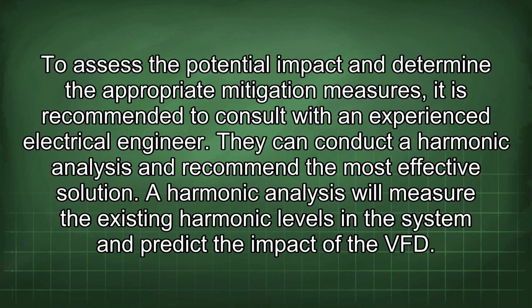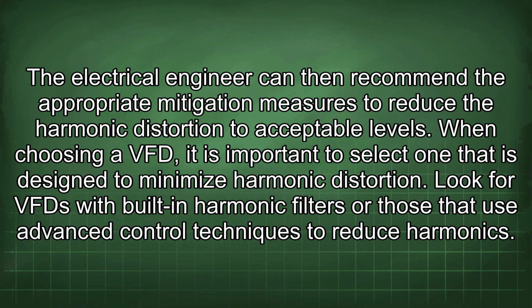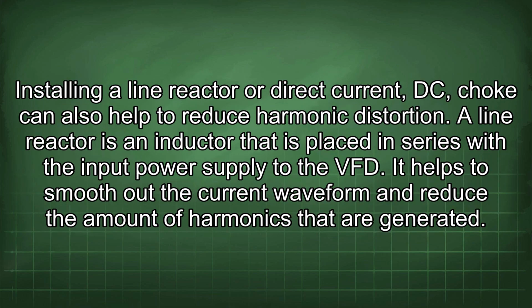To assess the potential impact and determine the appropriate mitigation measures, it is recommended to consult with an experienced electrical engineer. They can conduct a harmonic analysis and recommend the most effective solution. A harmonic analysis will measure the existing harmonic levels in the system and predict the impact of the VFD. The electrical engineer can then recommend the appropriate mitigation measures to reduce the harmonic distortion to acceptable levels. When choosing a VFD, it is important to select one that is designed to minimize harmonic distortion. Look for a VFD with built-in harmonic filters or those that use advanced control techniques to reduce harmonics. Installing a line reactor or direct current (DC) choke can also help to reduce harmonic distortion.